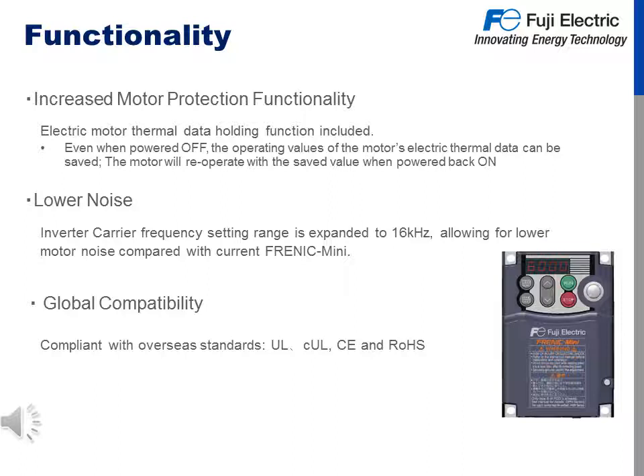Additional functionality with the Mini C2 includes increased motor protection in the form of electronic motor thermal data held function. If the power is turned off, the operating values of the motor's electric thermal data can be saved, and the motor will re-operate with the saved value when power is turned back on. Lower noise: the inverter carrier frequency setting range is expanded to 16 kHz, allowing for lower motor noise compared with the current Frenic Mini. For global compatibility, we are compliant with overseas standards such as UL, CUL, CE, and RoHS.